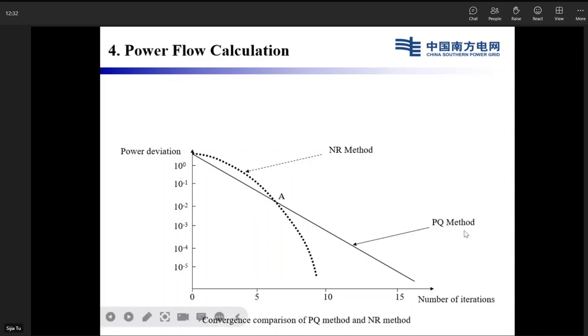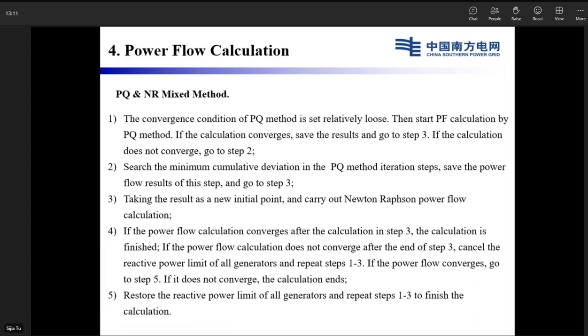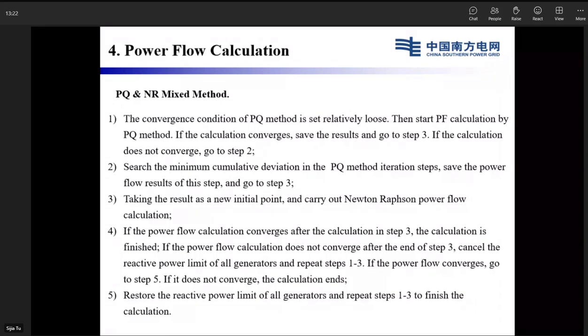This line is the PQ method. This curve is the NR method, Newton-Raphson method. We can see that at first the PQ method converges faster than the NR method, then the NR method converges faster. So in the DSP, we use the mixed method, combining both PQ and NR methods. The convergence condition of the PQ method is set relatively loose, so we start with the PQ method.